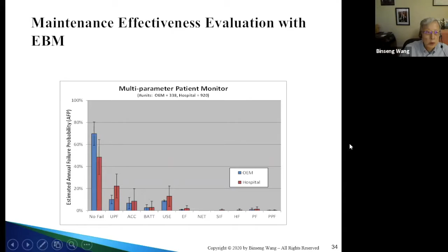Okay, so how do we use this information? We had 2 groups of hospitals where I used to work, and one group of hospitals followed the manufacturer recommendation, we call OEM, and the other group followed the hospital's own procedure and frequency of maintenance for patient monitors. And as you can see, these are totally different maintenance strategies. However, statistically speaking, they are not that different, because although the averages are different, the standard deviation bars show that the deviations are within standard deviation. So it's almost indistinguishable from the statistical point of view, and therefore these two maintenance strategies are equivalent, okay?